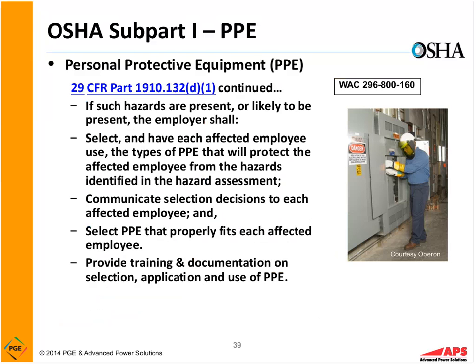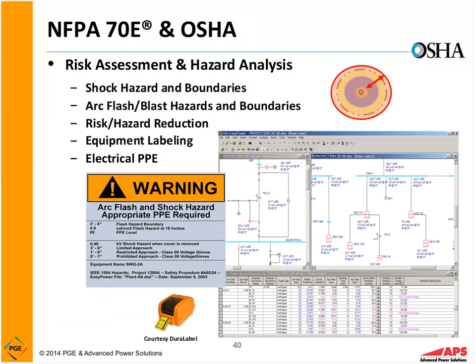So, if the hazards are present or likely to be present, the employer shall select and have each affected employee use the types of PPE that will protect the affected employee from the hazards identified during the assessment, communicate those decisions, select PPE that properly fits, in other words, size 4XL or 5XL doesn't work for everybody, and provide training and documentation in the selection, application, and use of PPE. And again, folks should have demonstrated knowledge that they can show that they know how to pick and use their PPE. So NFPA 70E and OSHA talk about risk assessment and hazard analysis. Now 70E will say you can do a study where you can actually calculate the incident energy level.